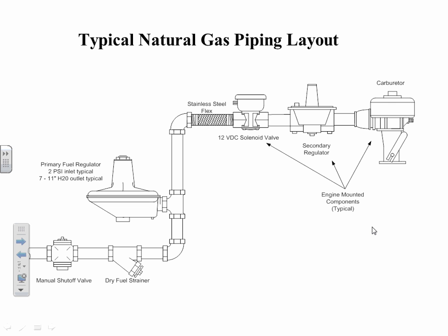Here's a sketch I did several years ago showing a typical gas system and what they look like on the engine. Got a manual shutoff valve. This is a dry fuel strainer. And there are particles that come through on the gas sometimes, and this little leg picks those up, and there's a plug on it. After you shut the valve off, you can do maintenance, pull that plug out, and drain any particulates that are in there. If you have mechanical contractors, they'll call that thing a dirt leg. So it's not as neat a name. Fuel strainer sounds better. Then comes into a primary regulator.